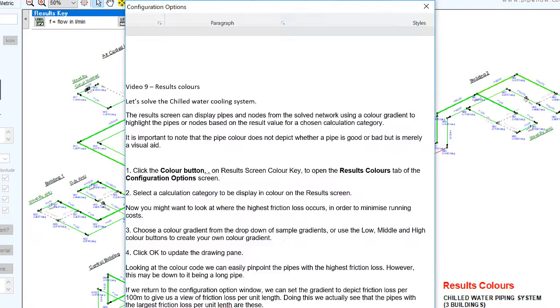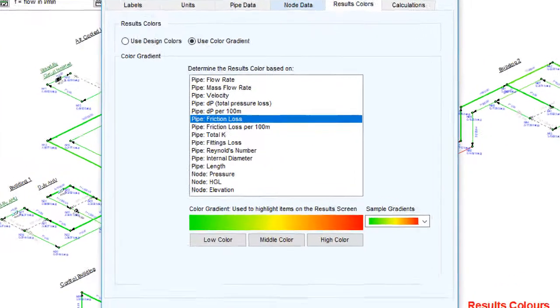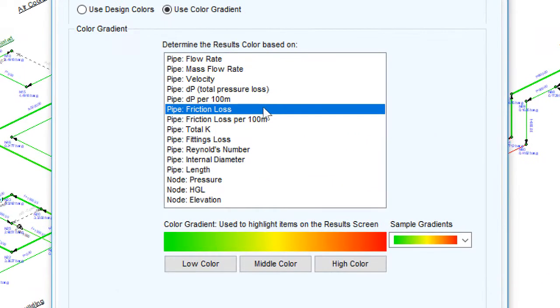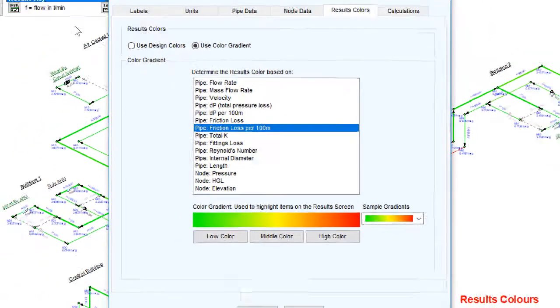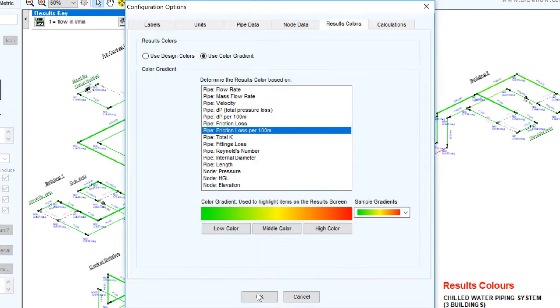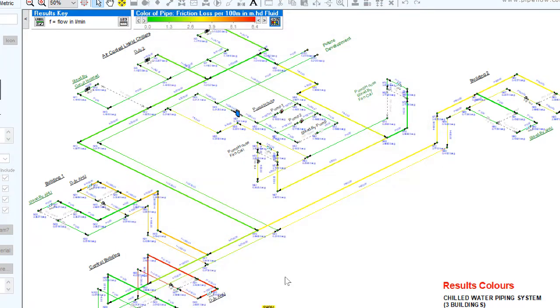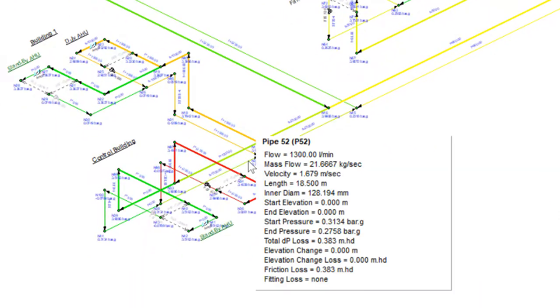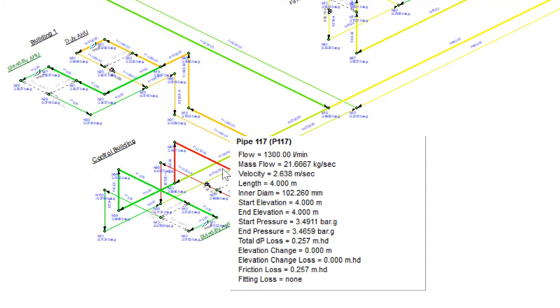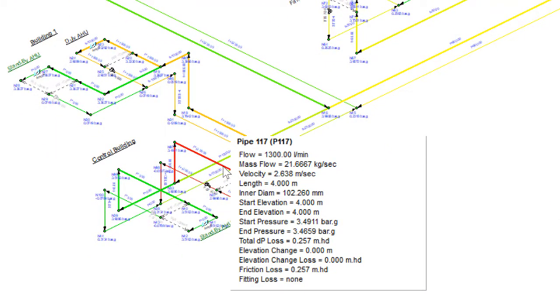If we return to the configuration options window, we can set the gradient to depict the friction loss per 100 metres. This will give us the view of friction loss per unit length. Doing this, we actually see that the pipes with the largest friction loss per unit length are these.